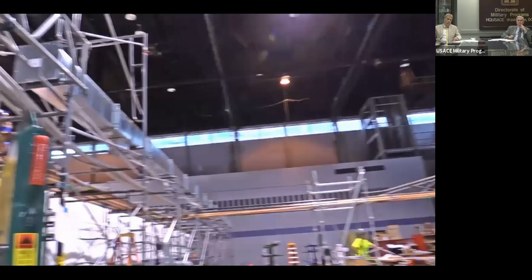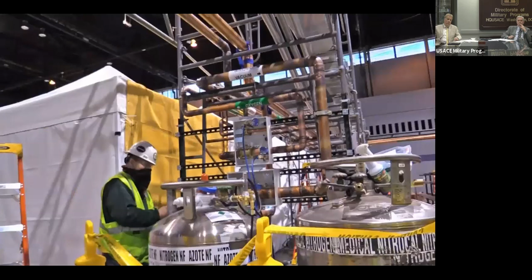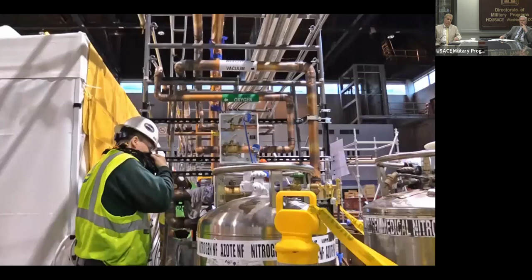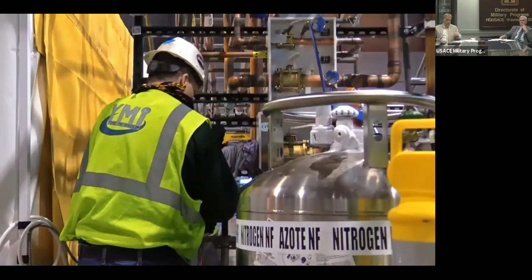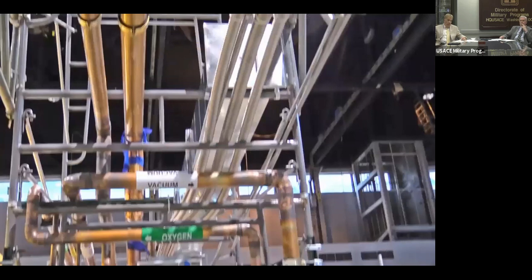What you see right next to them is nitrogen tanks—medical grade nitrogen—which they place into the pipe and put under pressure while brazing. The nitrogen keeps the inside of the pipe clean; there are no burns, nothing. When he's done, the outside of the pipe gets discolored because he's heating it to around 1,000 degrees, but that's just discoloring the exterior, not the interior, so the interior stays clean.